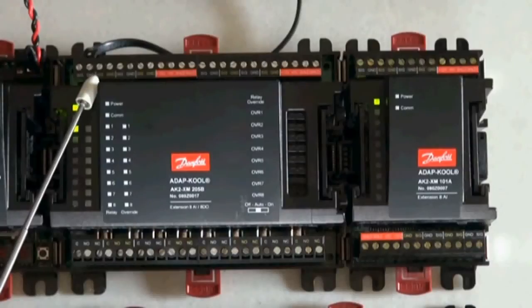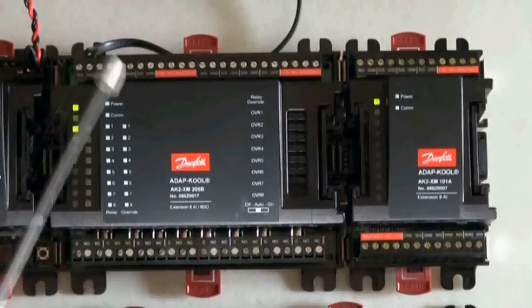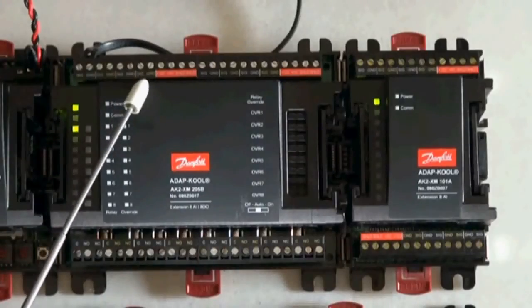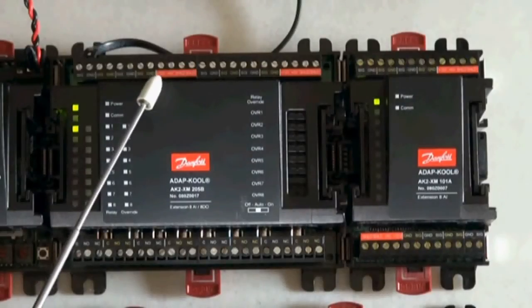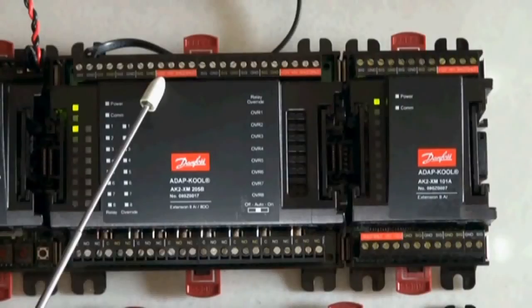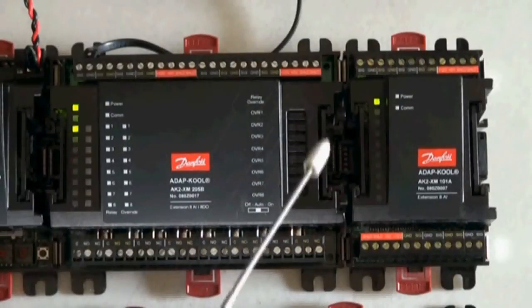At the top you have 8 inputs that can be used for pressure transducers, temp sensors, 0 to 10 volt inputs, and dry contact digital inputs. There are 2 locations where plus 12 volts DC is provided to power sensors, along with a plus 5 volt location for sensor power.